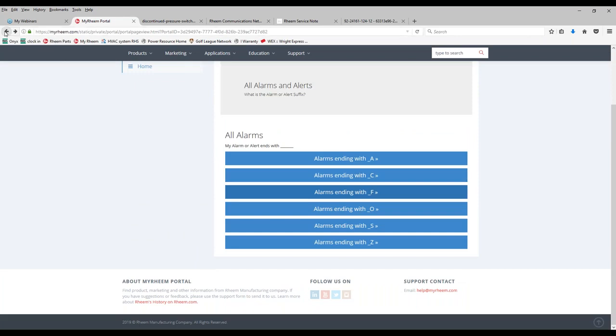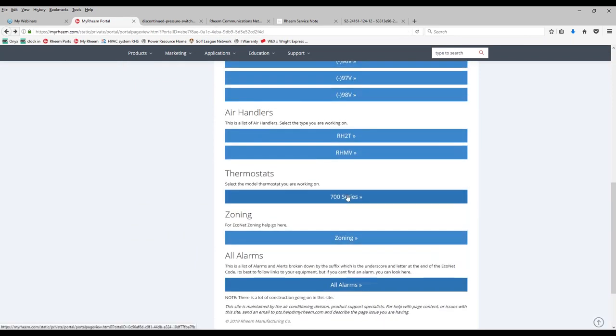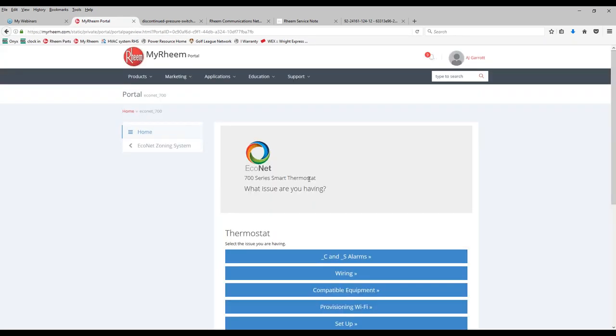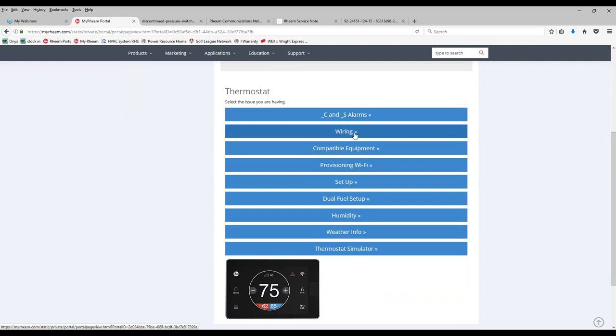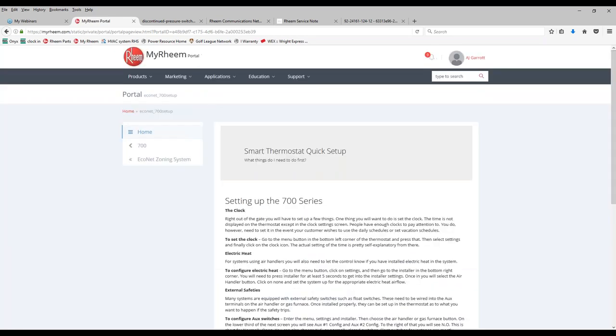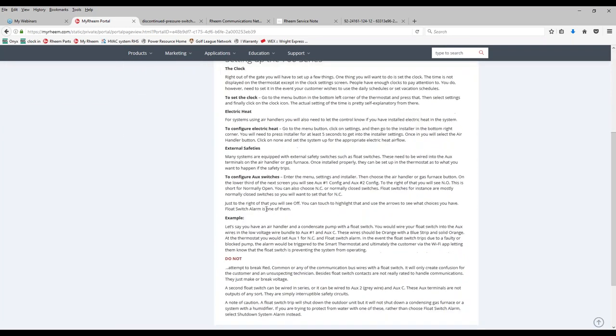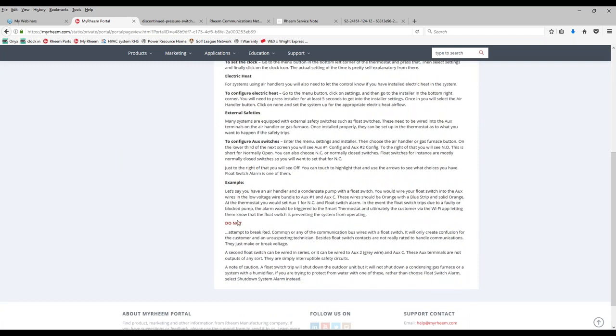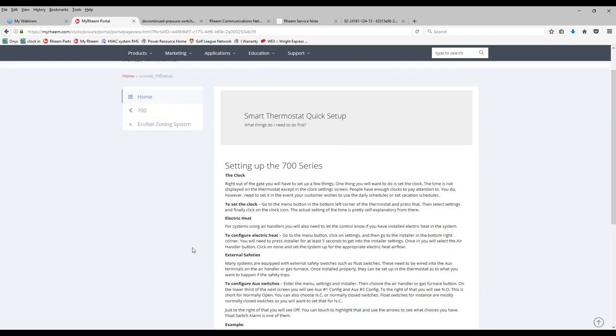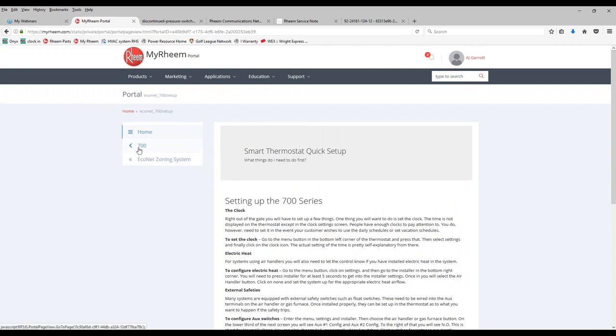One other important thing I'm going to show you is if you come to the thermostat, the 700 series thermostat, and you click on that, you can come down and see the alarms. You can check out the wiring on how to wire it, compatible equipment, provisioning the Wi-Fi, setup, dual fuel setup, humidity. So if you click on just say setup, it'll go through the information on setting up the clock, the electric heat, safeties, auxiliary switches built in, and it'll tell you what to not do with that setup. So good information there. We're going to go back to the thermostat.